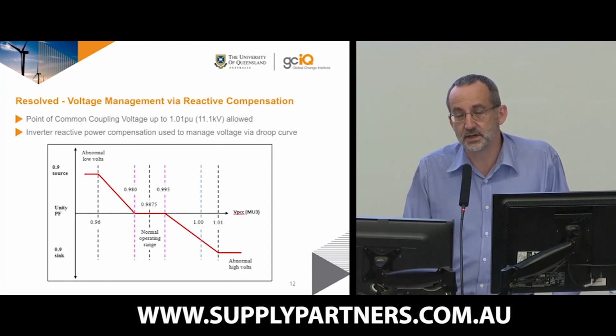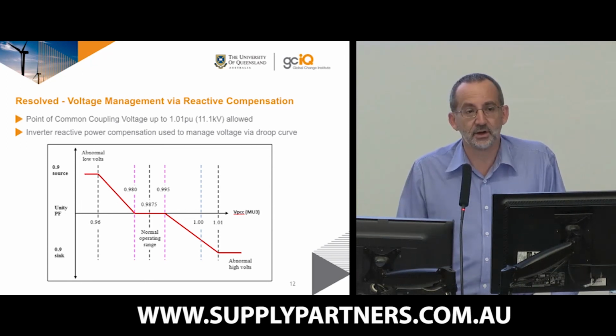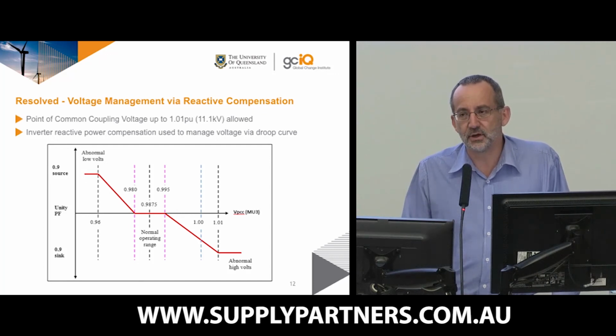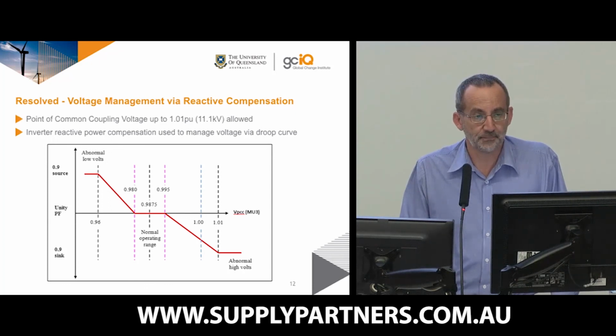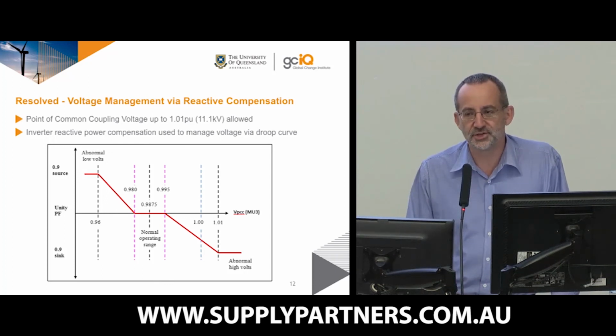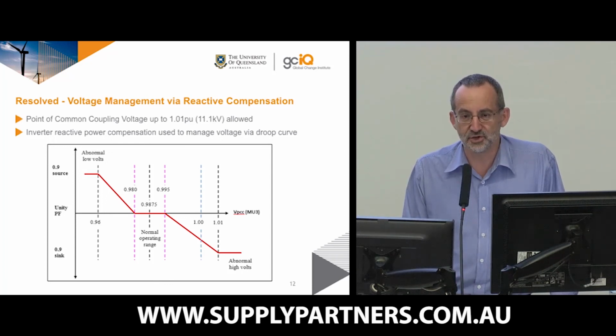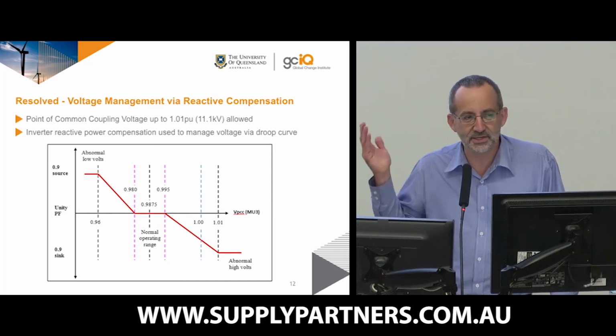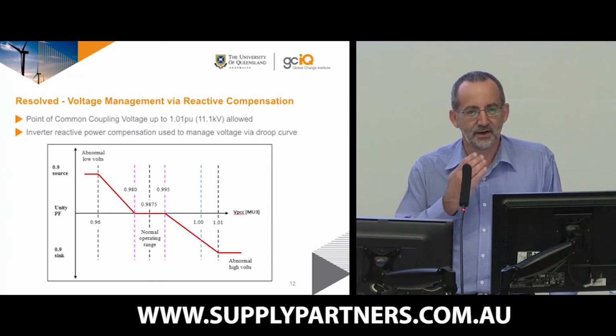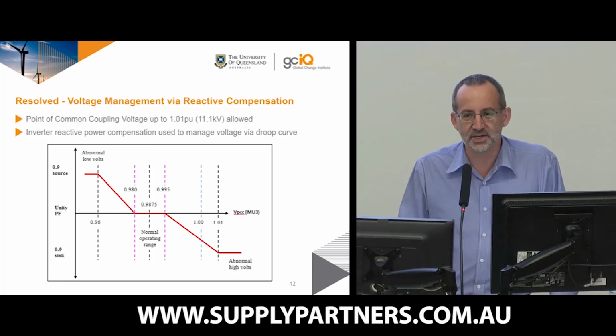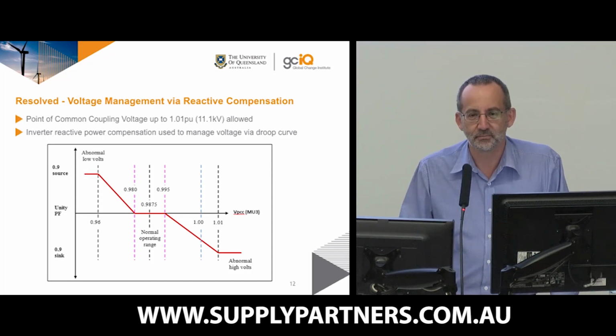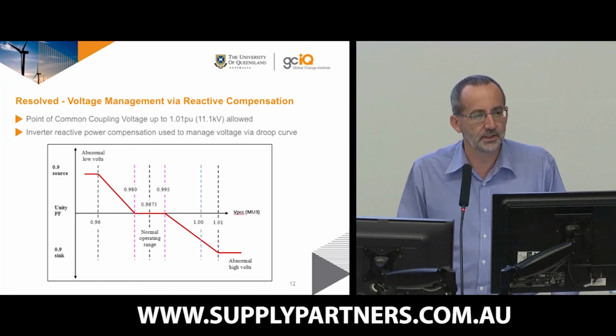Since earlier this year, the new connection standard in Queensland is trying to drive people towards configuring the inverters to 0.9, and I'm sure that a lot of inverter manufacturers will do that by default. I don't believe that's a good thing, because at the same time they've introduced a tariff to charge commercial customers for consuming reactive power. On one hand, they're saying it's bad, we're going to charge you for doing it. On the other hand, they're telling the PV installation industry, it's good, you better do it. You can't have both policies side by side.